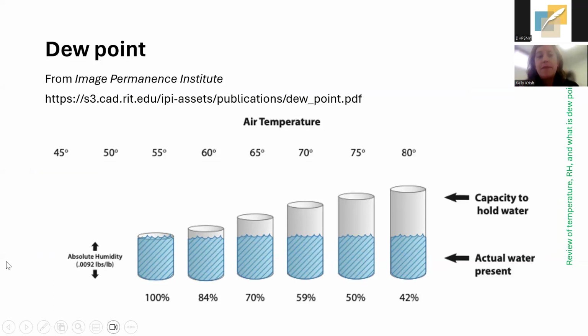So as I said, I spent a number of years at the Image Permanence Institute. This is one of their resources. I think it's also a really helpful visual when we start talking about how these three parameters interact. So in this example, the size of the buckets relates to the temperature. As the temperature increases, the bucket gets bigger. It can hold more and more. But the amount of moisture that's present in the air, think of that as your dew point. So in this example, the amount of moisture is constant across all of these buckets. Dew point's the same. We haven't done anything to change it. But as that container grows in size, the relative amount of space that the water is occupying compared to that empty space is decreasing. And that's what's meant by relative humidity.